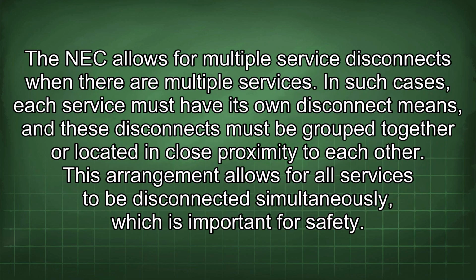The NEC allows for multiple service disconnects when there are multiple services. In such cases, each service must have its own disconnect means, and these disconnects must be grouped together or located in close proximity to each other. This arrangement allows for all services to be disconnected simultaneously, which is important for safety.